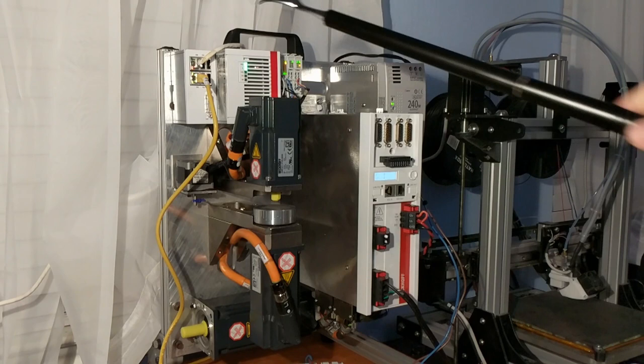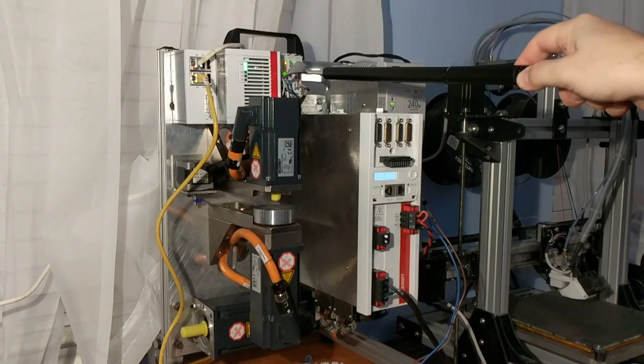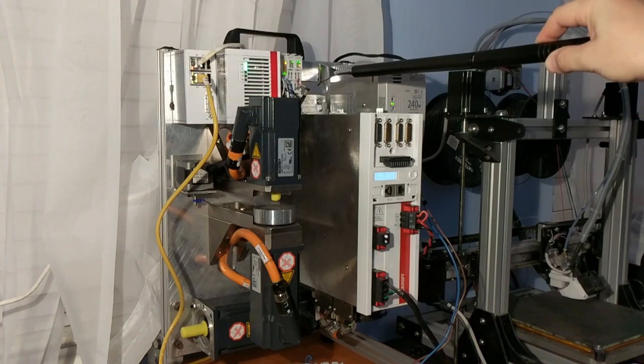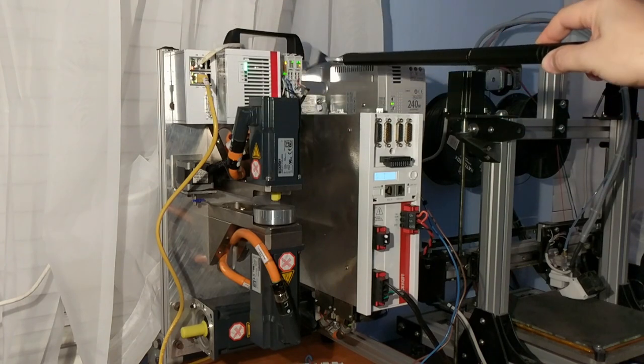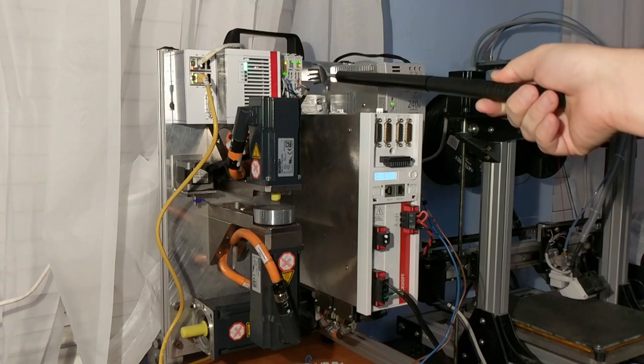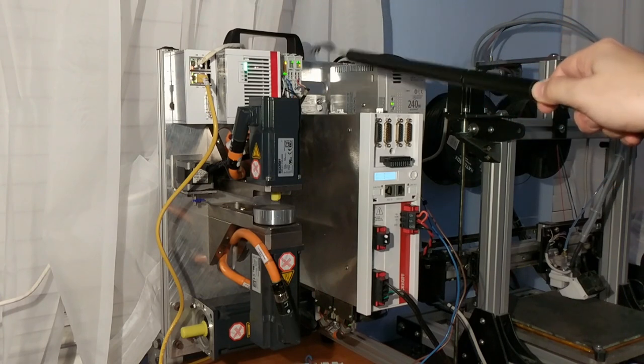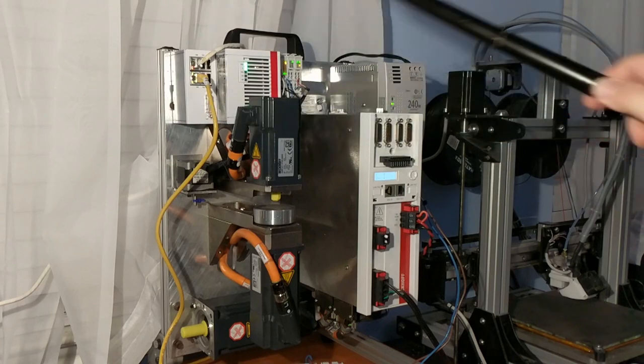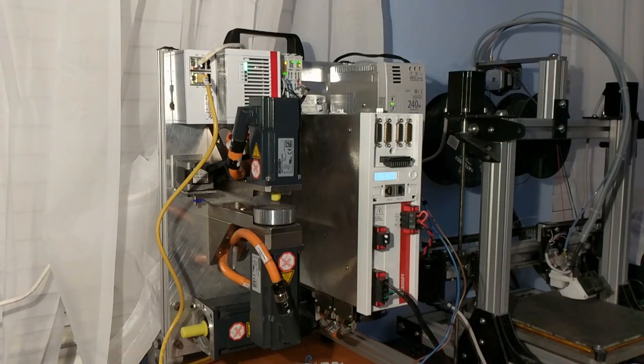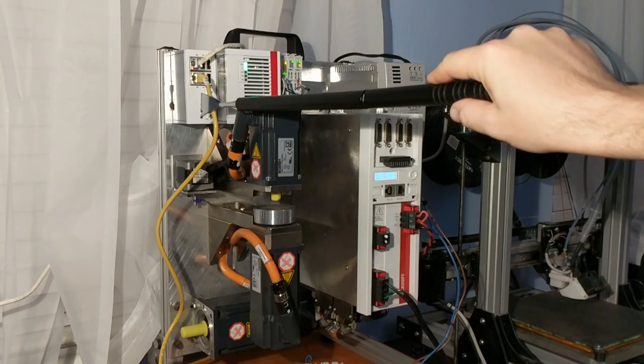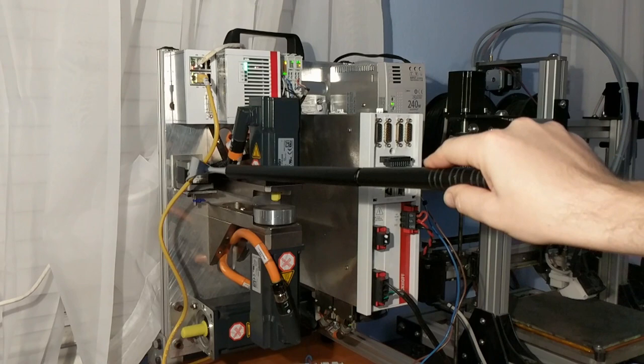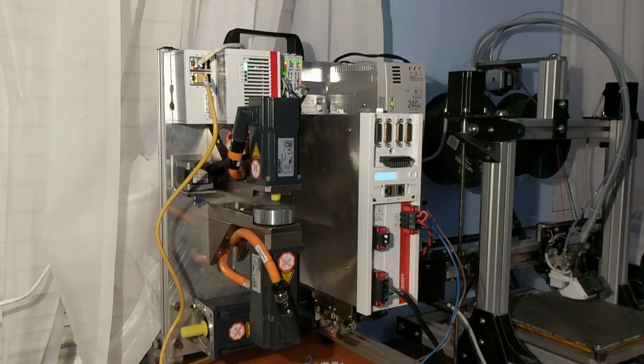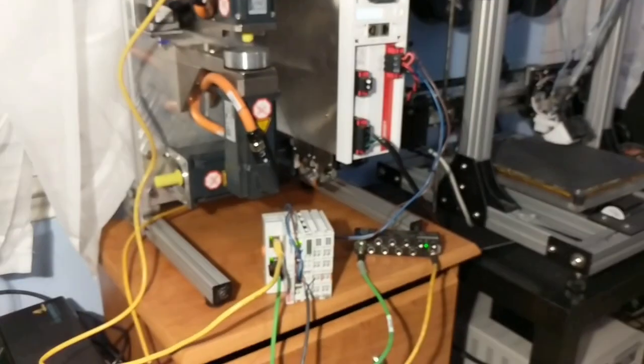So we pretty much just have this one here and then of course we've got the e-bus out this other side. For anything that's going to be in the cabinet with the PLC, we typically just run those e-bus slices right there and not bother with cables. But for servo drives and remote mounted stuff, you've got to have something to get this EtherCAT out to a cable. So we're going to dedicate this network card to be an EtherCAT master.